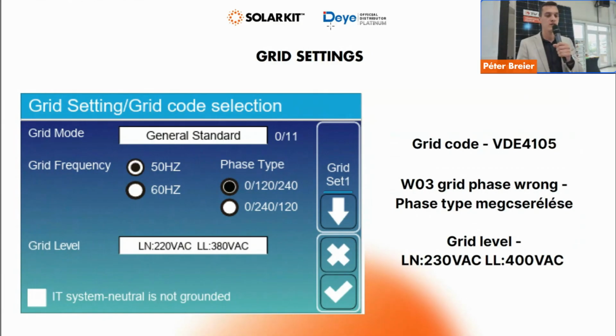If you have a W03 error code, that means that the grid phase is wrong. It's also written on the screen of the inverter. Then you just need to switch the phase type. When you try to do that, it will raise a warning that you may cause a malfunction or a direct error in the inverter if you do that. But please stay calm and just do that, because even if you do it in the wrong direction, it will not harm the inverter. Other than that, a grid level you should usually set to 230. I don't know of any countries that still have 220. Maybe there are some, but this one you need to check for your own country.